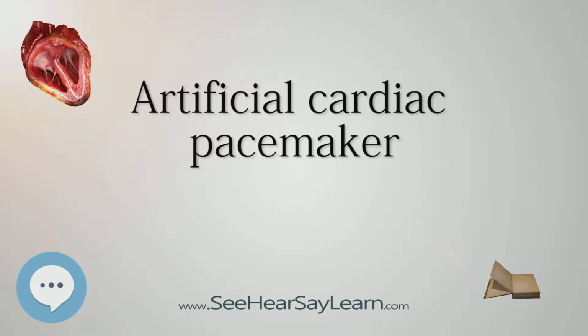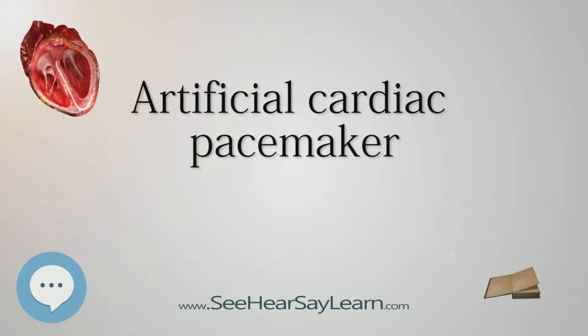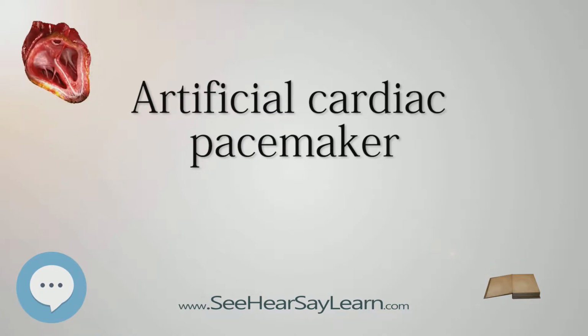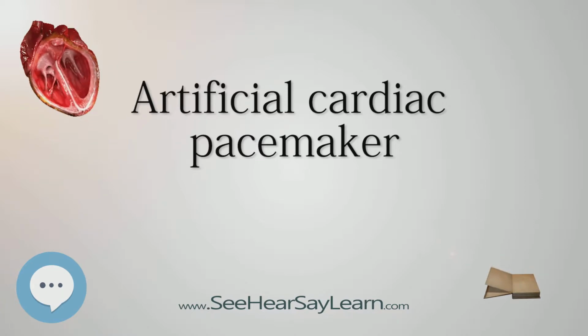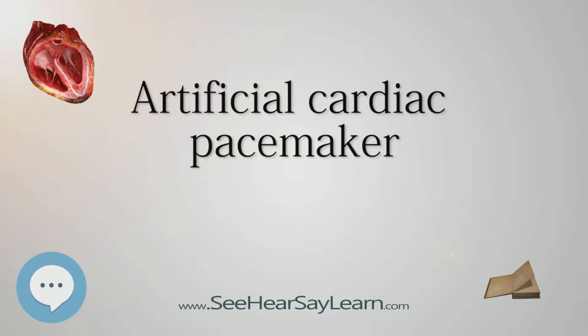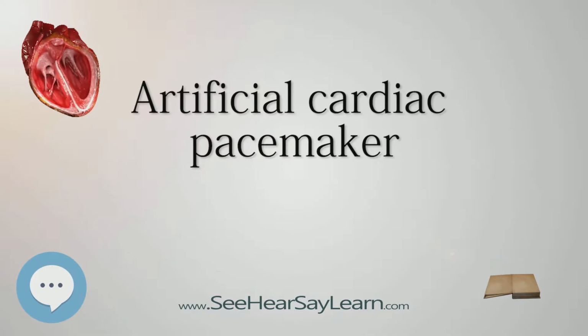This pacemaker has sensors that detect changes in the patient's physical activity and automatically adjust the pacing rate to fulfill the body's metabolic needs. Basic function. Modern pacemakers usually have multiple functions. The most basic form monitors the heart's native electrical rhythm. When the pacemaker does not detect a heartbeat within a normal beat-to-beat time period, it will stimulate the ventricle of the heart with a short low-voltage pulse. This sensing and stimulating activity continues on a beat-by-beat basis. The more complex forms include the ability to sense and/or stimulate both the atrial and ventricular chambers.